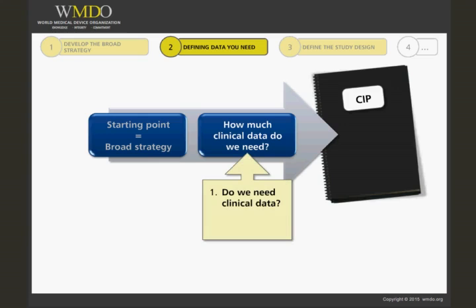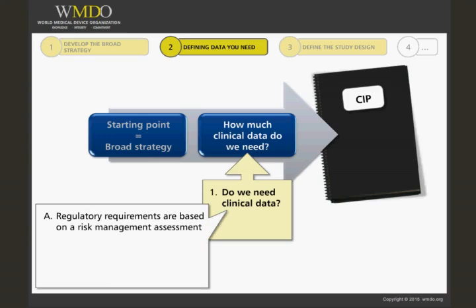Do we need clinical data? In most cases, the answer is yes. First, there are regulatory requirements which vary from one country or geographic region to another, but the basic principles always remain the same. This means that the extent and amount of clinical data needed is based on a risk management assessment. We can find further information about this in other WMDO courses.